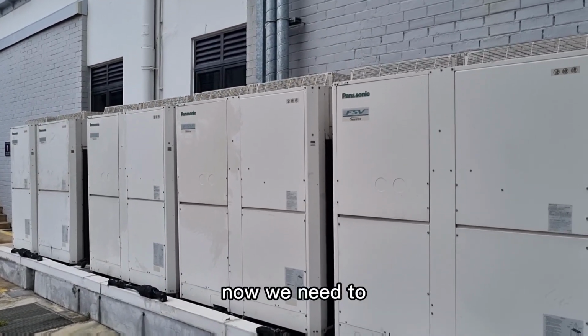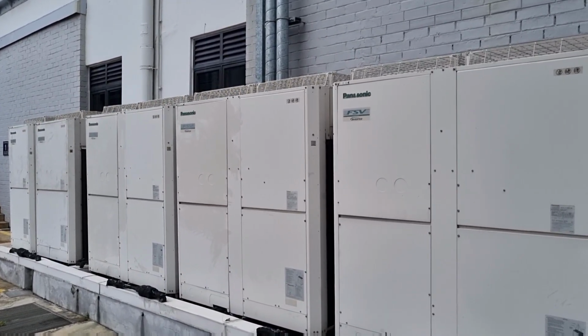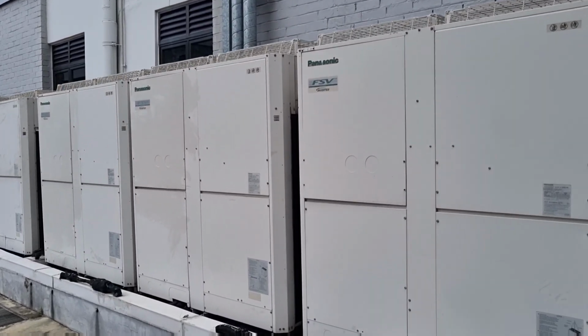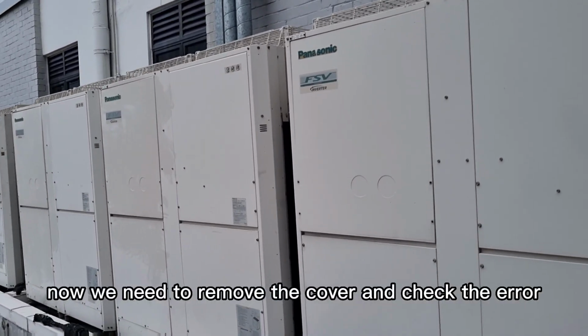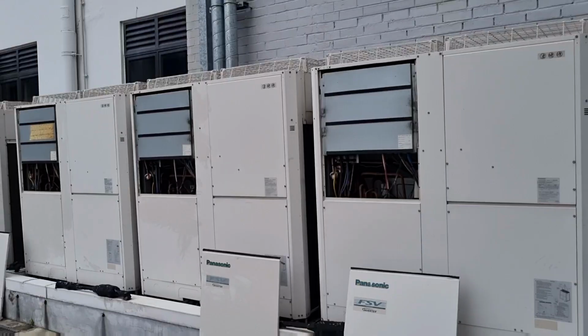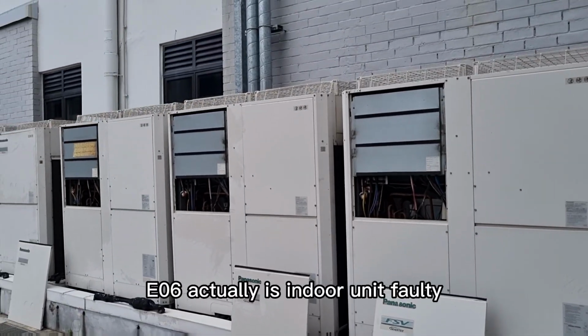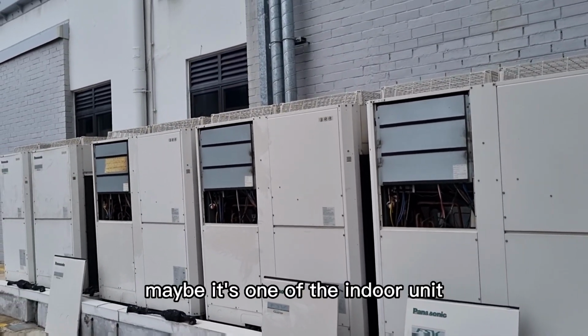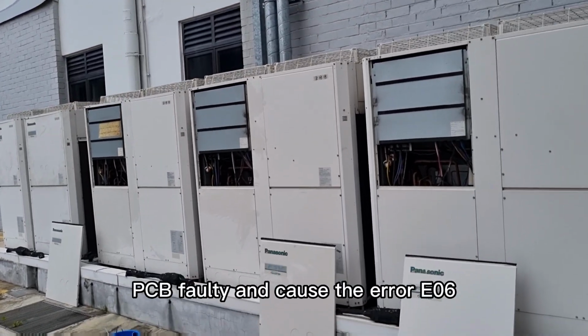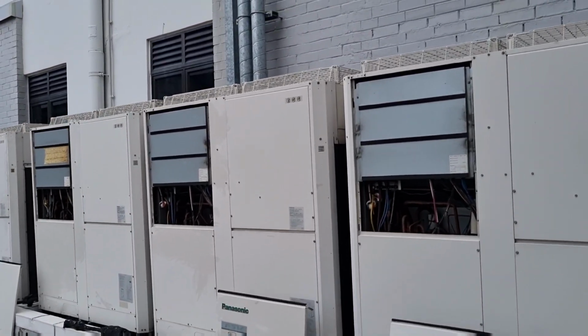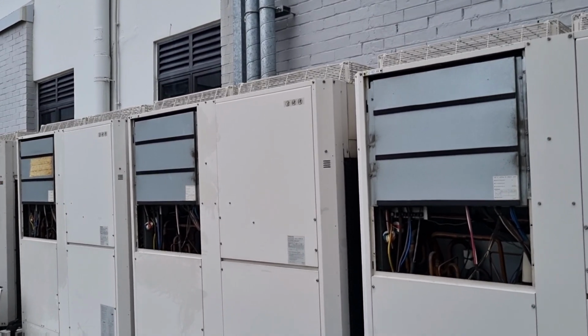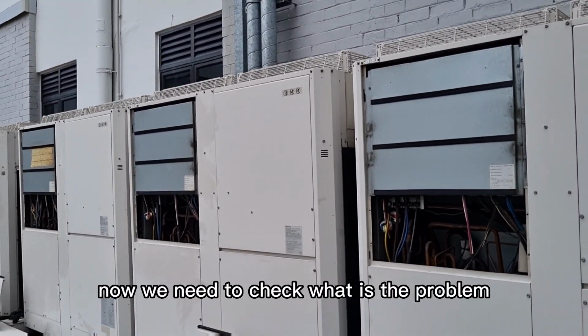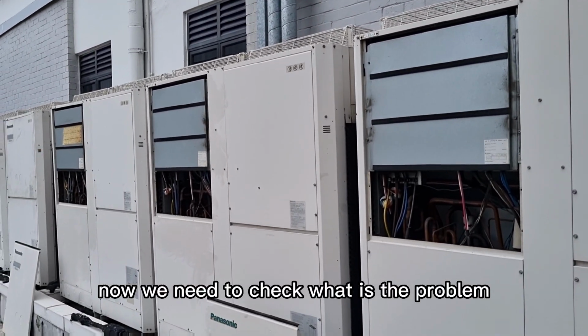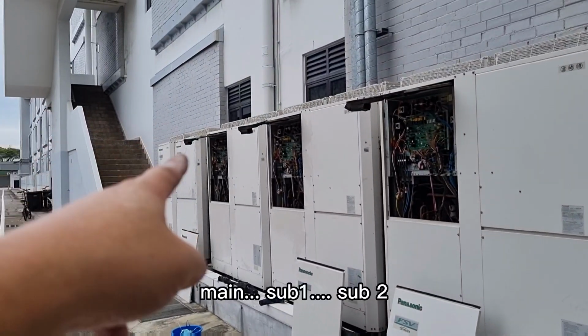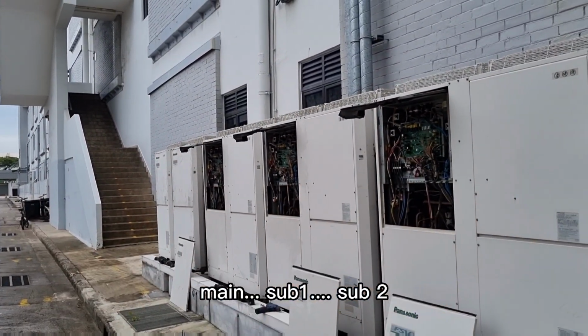Now we need to dismantle and check. We need to remove the cover and check the error. E06 actually is indoor unit faulty. Maybe it's one of the indoor unit PCBs that is faulty and causes the E06. Now we need to see what is the problem. Okay, main, sub 1, sub 2.